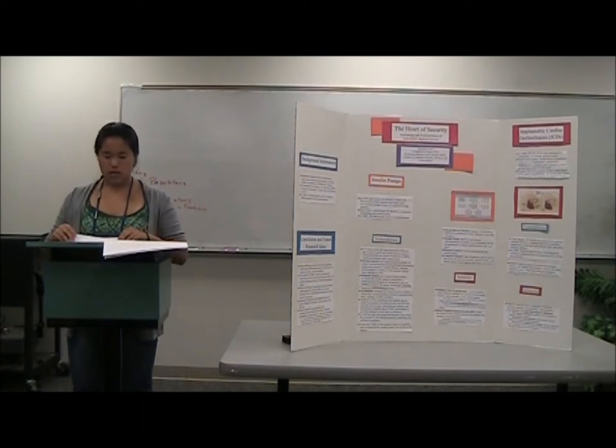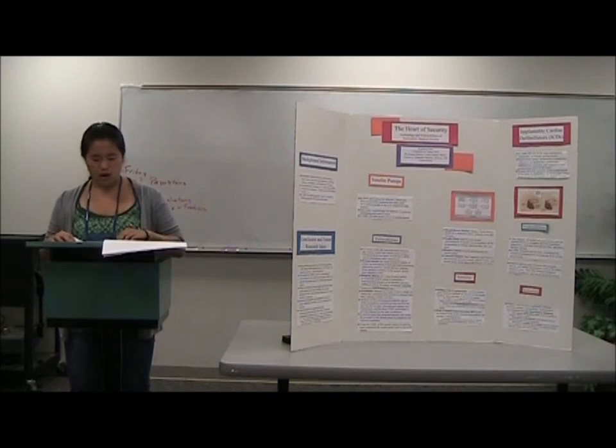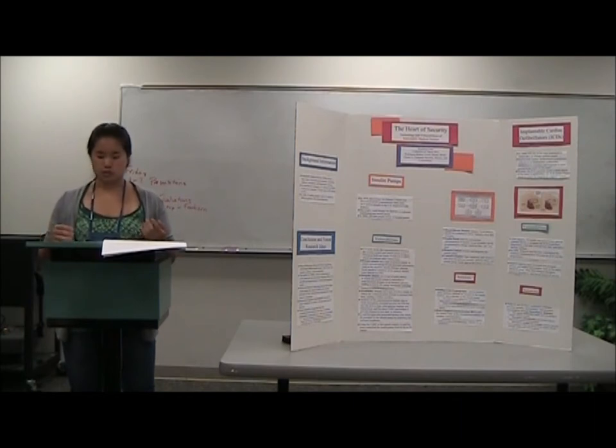So the Lee study suggests two possible defenses. One is cryptography. They suggest a rolling code cryptography in which the encoder is embedded in the remote control and the decoder is in the insulin pump, and the encryption key is shared. With a rolling code, it's difficult for adversaries to extract the device pin or launch replay attacks. But the degree of security does depend on the encryption algorithm.